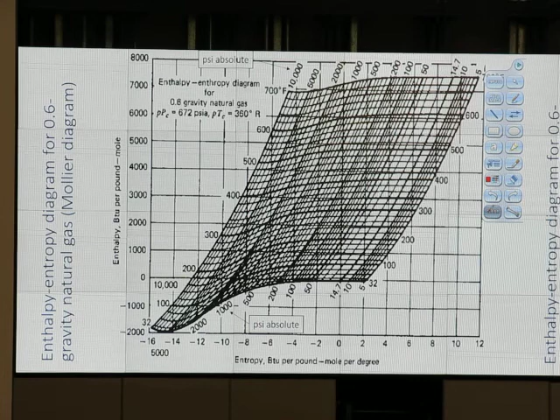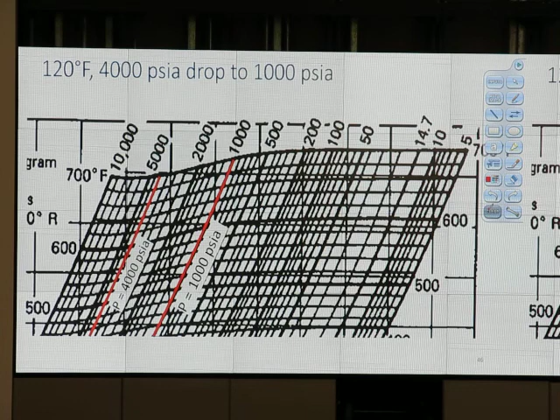Step number one, we have to locate the pressure and temperature at the inlet. Let me zoom in. I know that pressure at the inlet is 4,000. Pressure before the choke is 4,000 and after the choke is 1,000. So I locate them and draw a line, just follow the line. Then I locate the temperature at the inlet, which is 120, and draw another line. The point where 4,000 crosses 120 is this point. That is the upstream condition, before the choke.